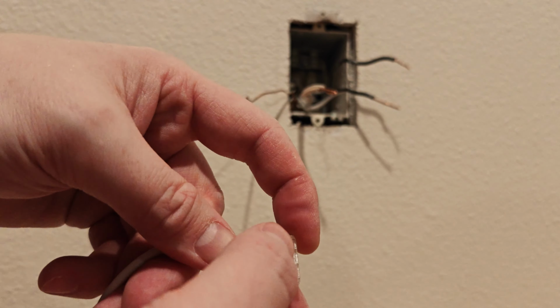Something to note here, Wago connectors bridge all of the wires in the connector together. For each of the line, neutral, and ground wires, you're going to want to have a separate connector that only contains the solid and stranded wires for that type. Do not connect any combination of line, neutral, and ground together, otherwise you're going to have a bad time. And by bad time, I mean fire.